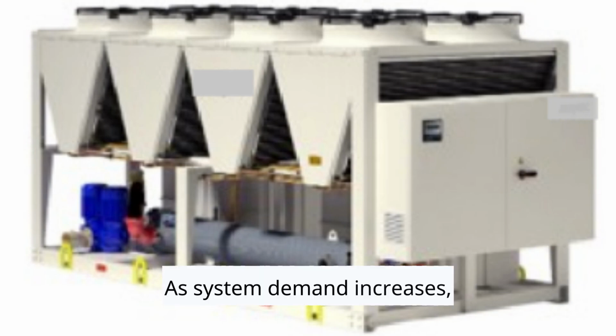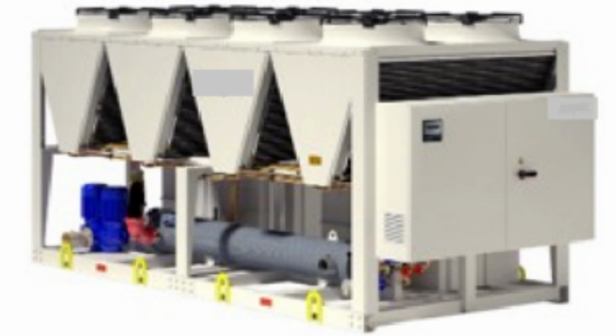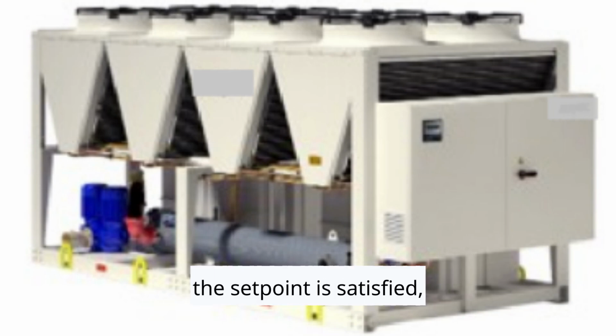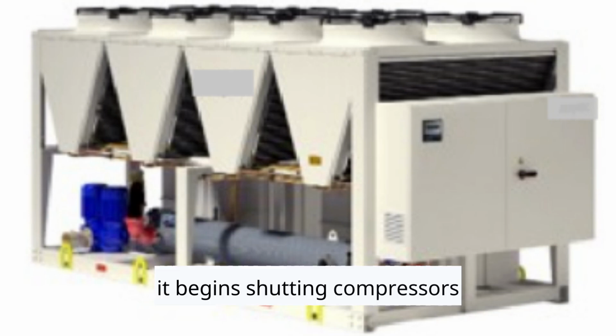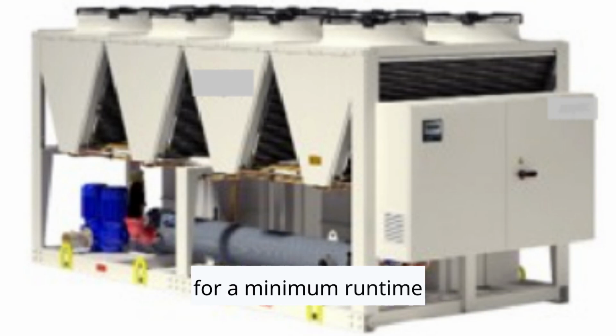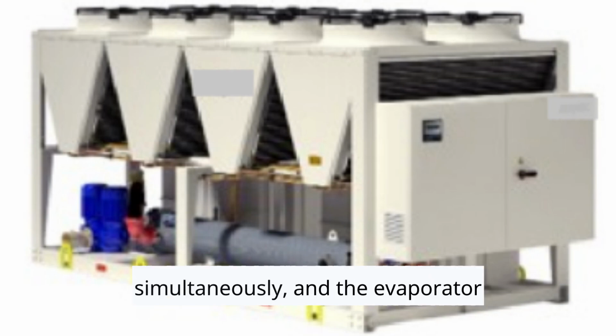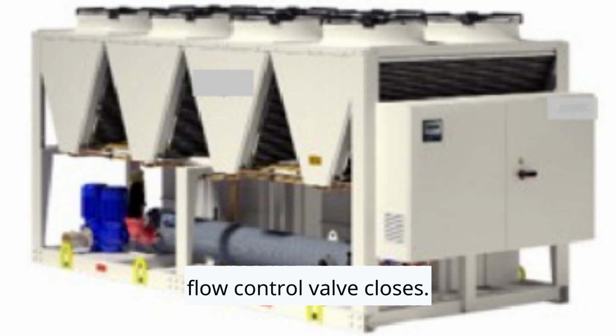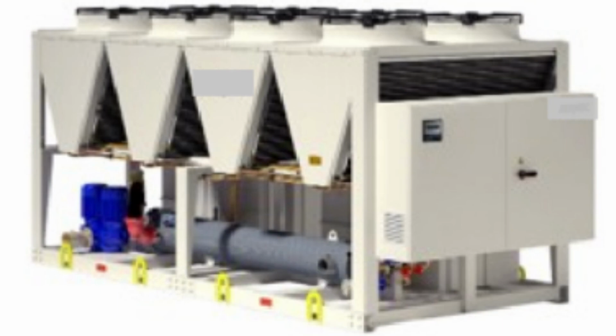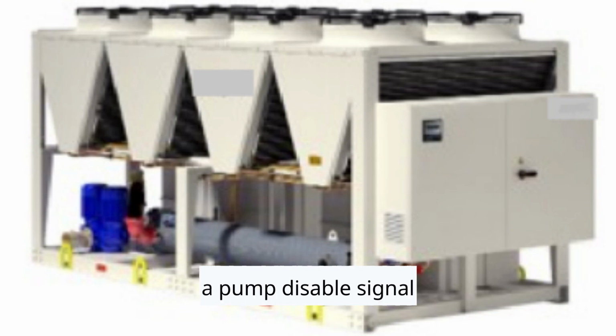As system demand increases, the controller brings additional compressors online to meet the load. When demand drops and the set point is satisfied, it begins shutting compressors off one by one. Each compressor must run for a minimum runtime to ensure proper oil return before it can stop. When a compressor shuts down, the condenser fan or modulating valve stops simultaneously, and the evaporator flow control valve closes. Finally, the controller sends a pump disable signal to turn off the associated pump.